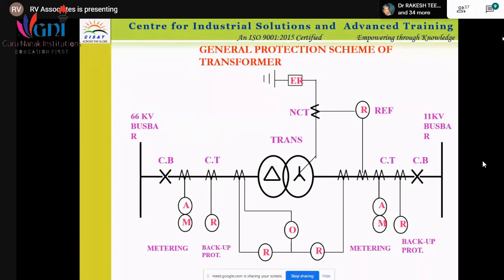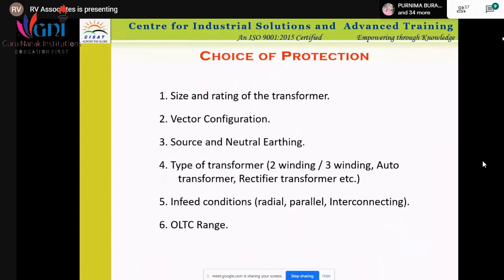Differential protection is used for internal faults. Please note that a winding fault is monitored and tripped. An external fault is not tripped by the differential protection. In that case, restricted earth fault protection or short circuit protection is to be used for external faults. This is the choice of protection based on the size and rating of the transformer. It depends on the application, the transformer size, or the rating. Power transformers or industrial transformers are normally in the range of a minimum 2 MVA. It can go up to 100, 200 MVA transformers.